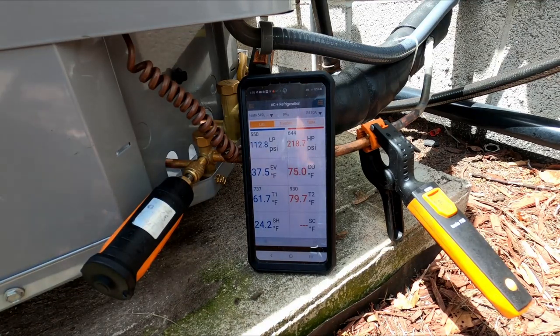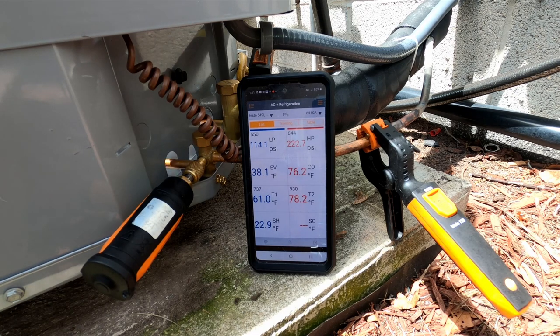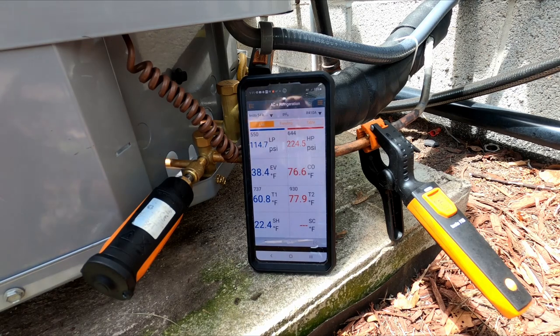It's funny. I know this is less than 15 feet of line set. We don't have a leak. And it states in the manual it's pre-charged for 15 feet of line set. And I'm low. How is that possible? And no subcooling. Let me let it run, but it's looking low, because I need 10 degrees of subcooling. I ain't gonna make it. Maybe 5 or 4.